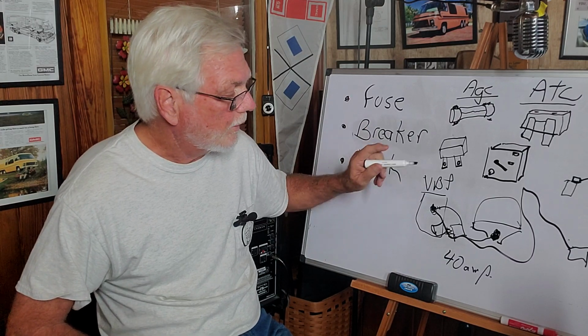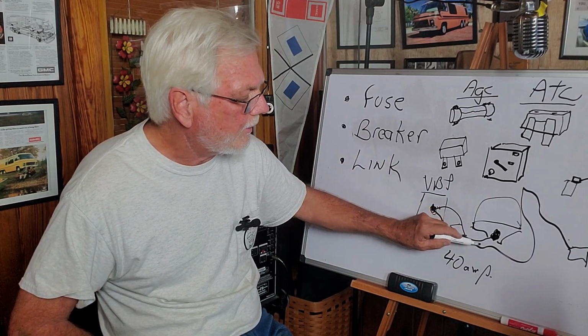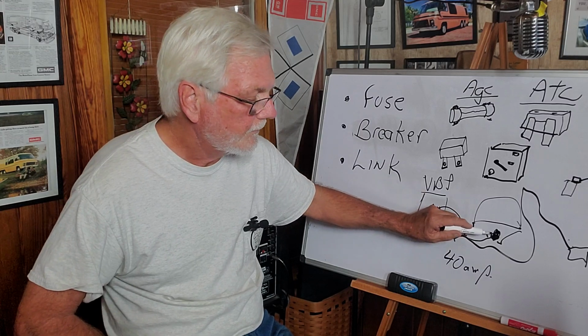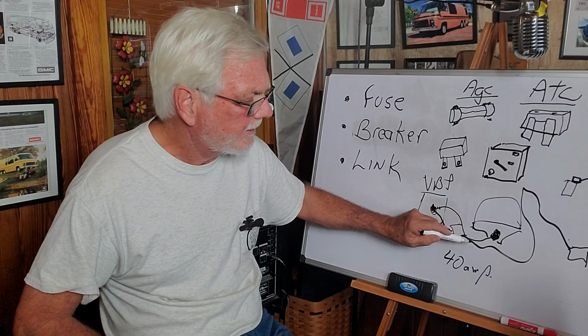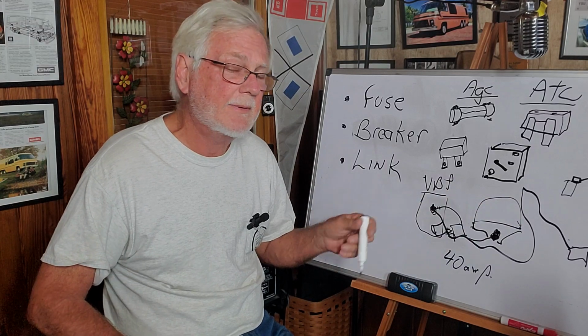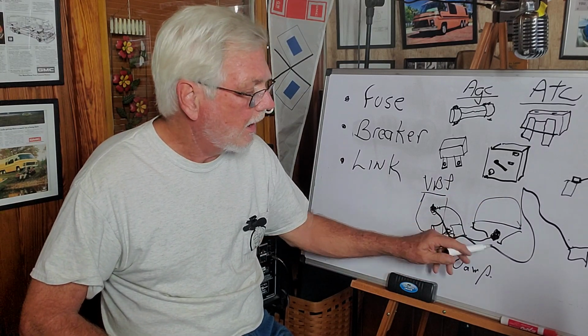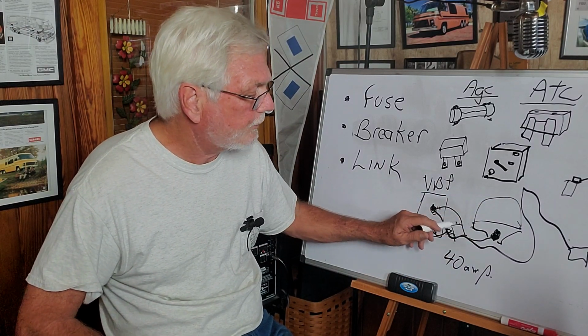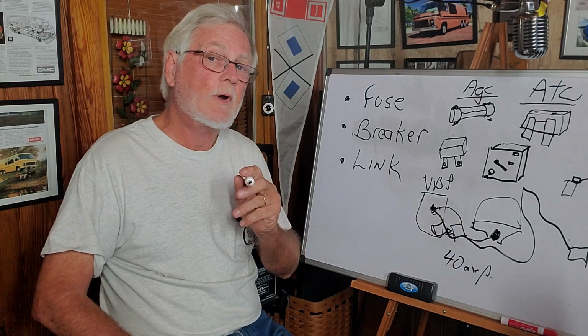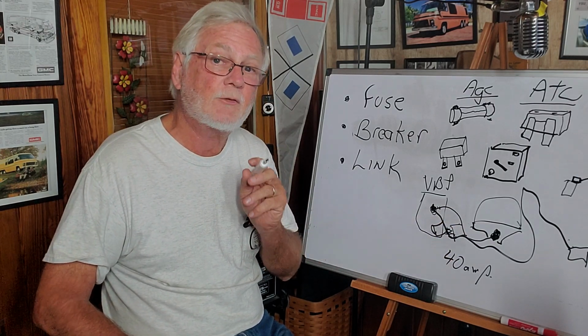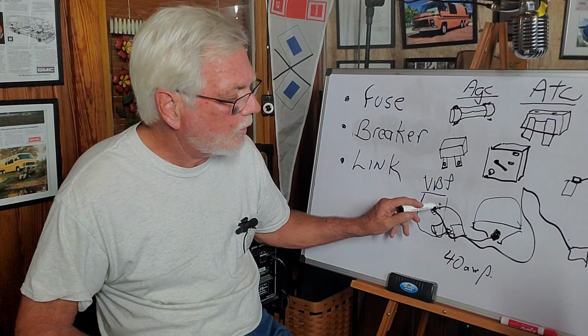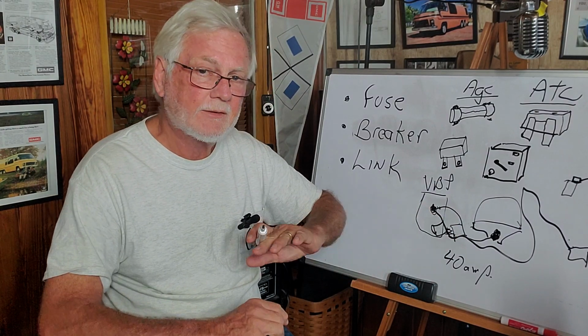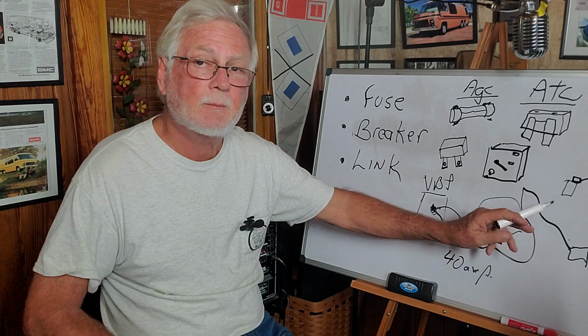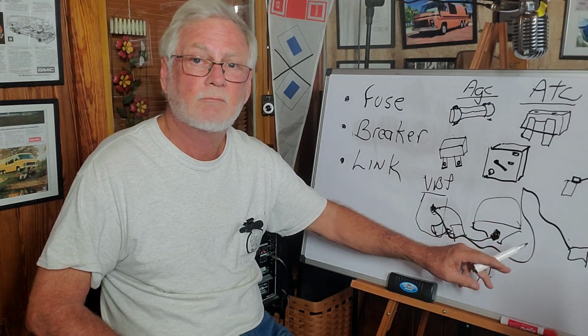Okay, what that does is take that load off of this, the replacement of the fusible link. That knocks out maybe 20 to 25 amps of current going through that circuit. So a 40 amp fast blow fuse would be more than enough protection for the entire electrical system if the compressor was taken off the circuit.